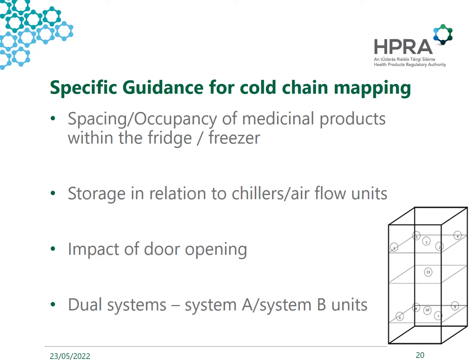And then finally, think of the operation of equipment. For example, is there a dual system - system A and system B - that rotates while one is in defrost? Has this been captured and planned for in the protocol and subsequently in the report? How will it work - is it a manual changeover or is it automatic? When will it happen, and is that changeover impacting on the temperature at all? It's important that's evaluated within the actual study.